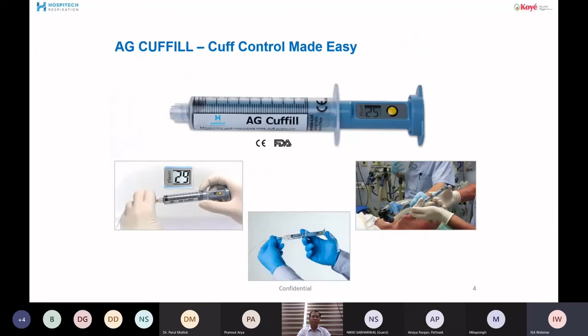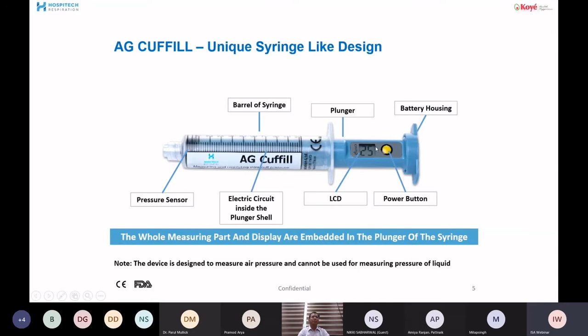Now, we are used to handling a 10 cc syringe for inflating and deflating the endotracheal cuff. This is a 10 cc syringe with a difference. There is a battery embedded in the plunger. An LCD display is attached to the plunger. There is an electrical circuit inside the barrel of the plunger and a pressure sensor at the tip of the plunger. Thus, when it is connected to the pilot tube, you get an accurate reading on the LCD display.